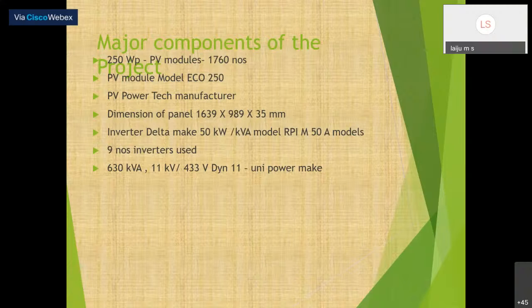So how many inverters are required for obtaining the 400 kW? I had already said that we had used the panels such that we can produce a maximum of 440 kW. So how many inverters are required to meet that condition? So we are selecting 50 kW and the model is RPI M50A, from which the capacity is 50 kW. So a total of around 440 or 450 kW of inverters has been connected. So 9 such inverters are placed to make 440 kW capacity.